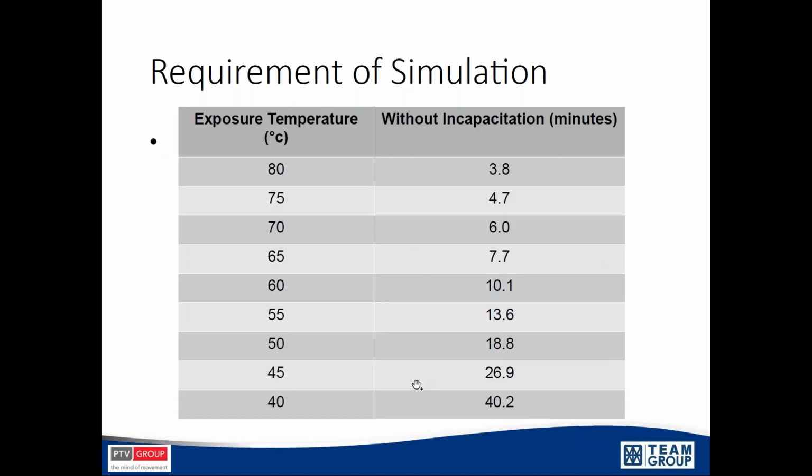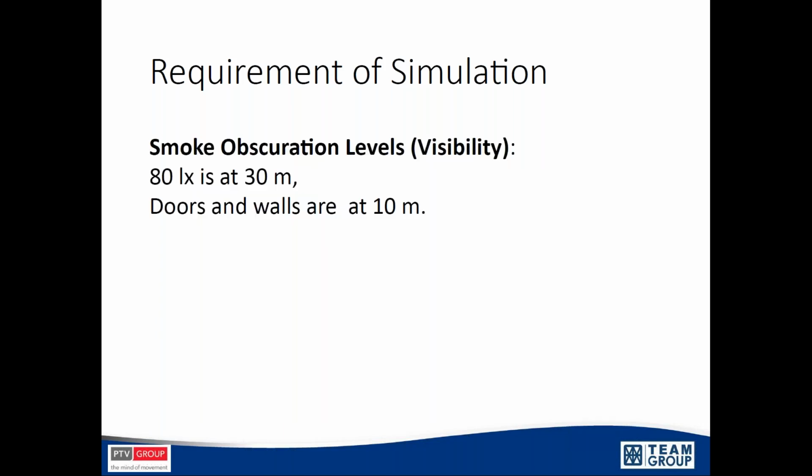Okay, next is about exposure time to the heat. At the heat of 80 Celsius degrees, passengers can stand not longer than 4 minutes. And about the visibility because of the smoke, it requires 80 lux at 30 meters.